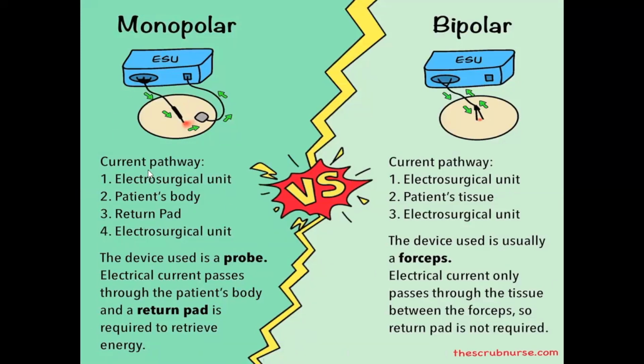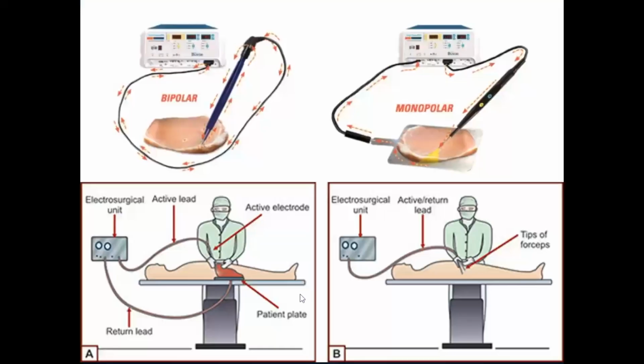So in monopolar, the current pathway is from the electrosurgical unit via the patient's body to the return pad, then back to the electrosurgical unit. But in bipolar: electrosurgical unit, patient tissue, electrosurgical unit. It doesn't take a longer route. Okay. Again, in bipolar, you can see the current comes from here, goes to the tissue, just goes between the two electrodes and then goes back to the electrosurgical unit. But in monopolar, it comes one way, cuts, goes through the patient's body to the earth plate, then goes to the electrosurgical unit.